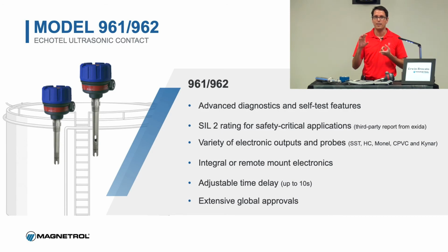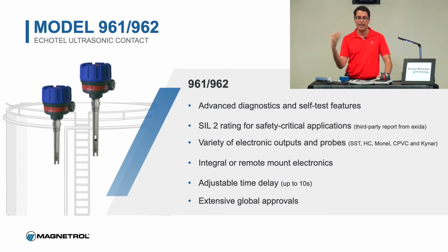SIL rating for this device, very important. If you want a SIL rated device at a low cost, this is the way to go. I already talked about the self-diagnostic and the self-test features. Different probes: if you want a really low-cost probe, we can do a polymer probe. The one that you see here is stainless steel, but we can do a polymer. I believe we do CPVC, so it's even lower cost. So if you have a strong base or an acid or anything like that, and you do not want to use Monel or Hastelloy, we can go down to CPVC or Kynar if the temperatures and pressures permit the use of a polymer. Then again, the remote electronics and the time delay as well.